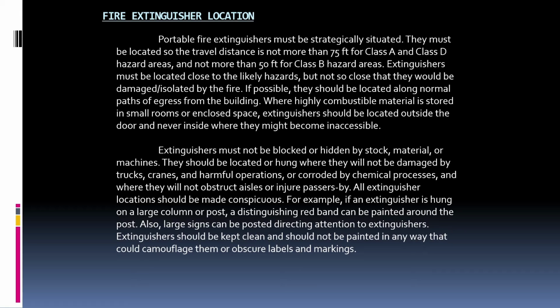Extinguishers should be located outside the door and never inside where they might become inaccessible. Extinguishers must not be blocked or hidden by stock, material, or machines. They should be located or hung where they will not be damaged by trucks, cranes, and harmful operations, or corroded by chemical processes, and where they will not obstruct aisles or injure passers-by.